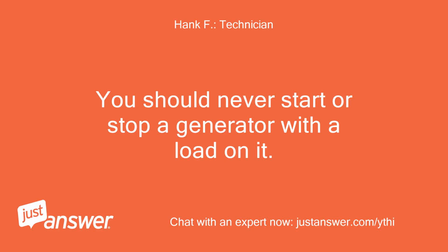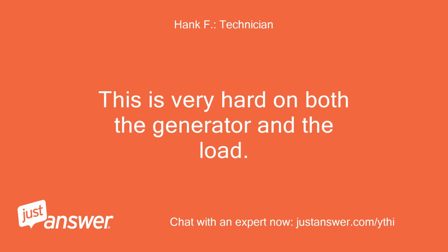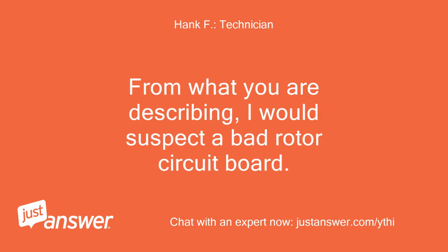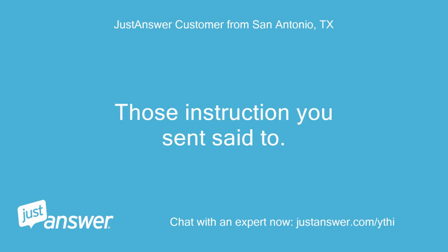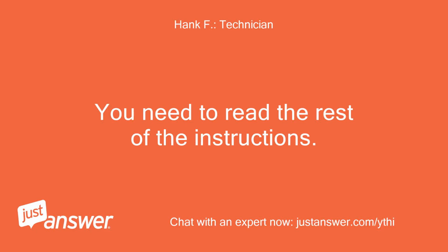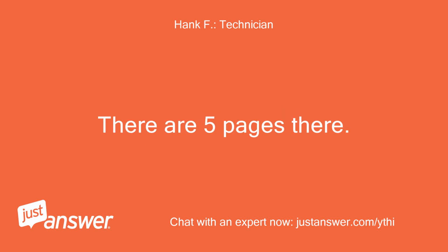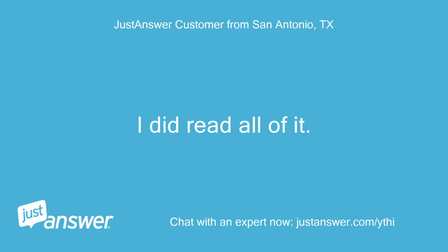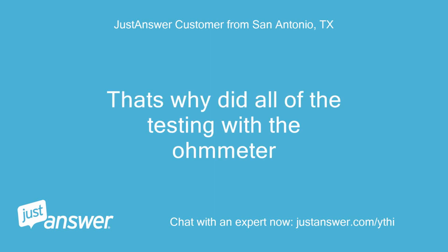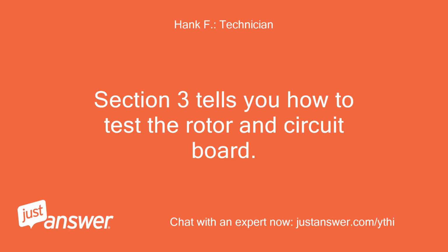You should never start or stop a generator with a load on it. This is very hard on both the generator and the load. From what you are describing, I would suspect a bad rotor circuit board. Those instructions you sent said to... You need to read the rest of the instructions. There are 5 pages there. I did read all of it. That's why I did all of the testing with the ohmmeter. Section 3 tells you how to test the rotor and circuit board.